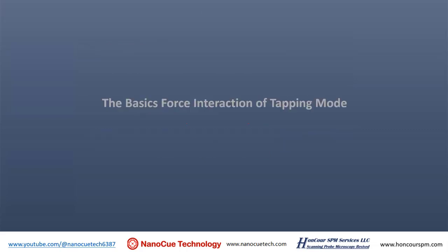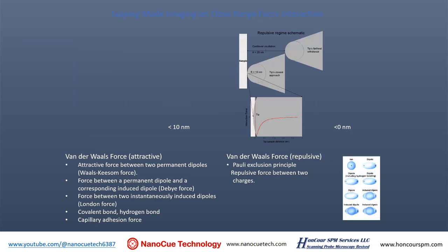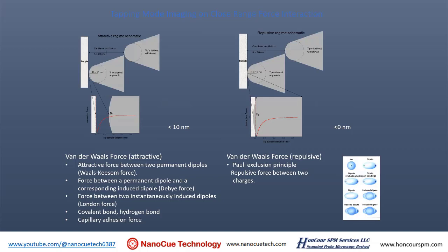The basic force interactions of tapping mode: when the tip approaches the sample at a certain distance, the molecules at the end of the tip and the molecules on the sample experience attractive force when this distance is around 10 nanometers. As the tip gets very close, it invades the sample space and the attractive force turns into repulsive force. The attractive force is the van der Waals force, with a range of about 10 nanometers. The repulsive force occurs when the tip-sample distance is below a nanometer — they're essentially invading each other.